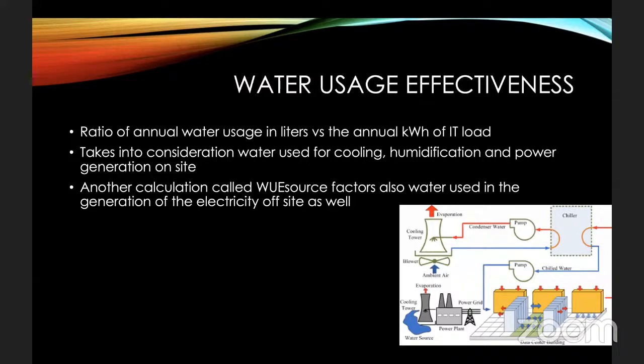So for example, a WUE of 2 means for every 1 kilowatt hour of electricity that you're using for your IT load, you are consuming 2 liters of water to cool it. So there's another calculation, which is more accurate and complete, known as WUE source. This also takes into consideration the amount of water used to generate the electricity off-site as well. So by looking at this metric, you will be able to identify how efficiently your data center is using the water.